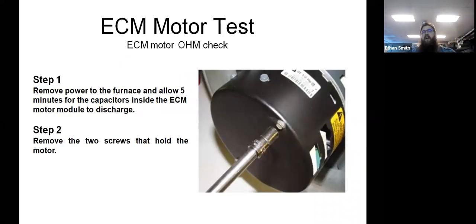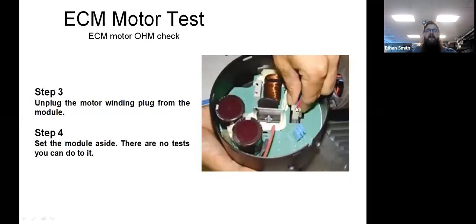Okay. So after we've done our go, no go test, that should cause our motor to turn on and spin in cooling speed. If it does, we know that the motor is okay and the frequency drive is okay. At that point, we know we've got a control board problem. Conversely, if it doesn't turn on the motor, now we need to get into the brains of the backside of the motor and do a couple things. One of those is an ohm check. So once you take the end bell off that motor, you'll have a little module in there. There's a picture of an older one.